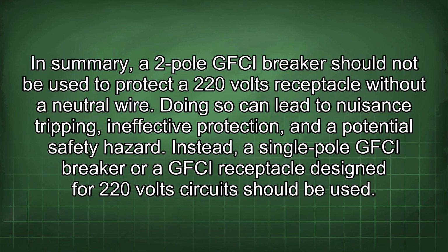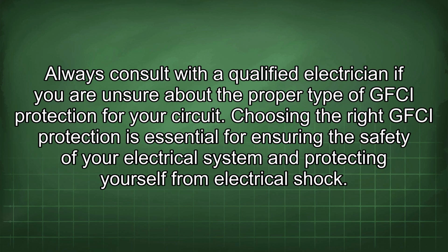In summary, a 2-pole GFCI breaker should not be used to protect a 220 volts receptacle without a neutral wire. Doing so can lead to nuisance tripping, ineffective protection, and a potential safety hazard. Instead, a single-pole GFCI breaker or a GFCI receptacle designed for 220 volts circuit should be used. Always consult with a qualified electrician if you are unsure about the proper type of GFCI protection for your circuit. Choosing the right GFCI protection is essential for ensuring the safety of your electrical system and protecting yourself from electrical shock.